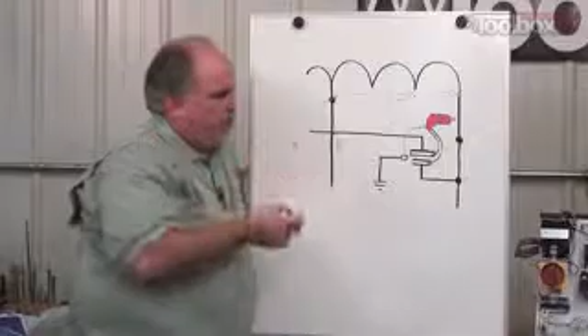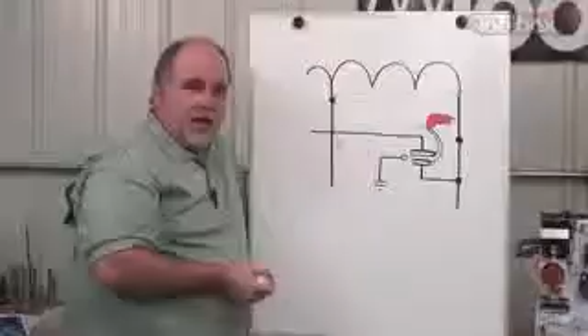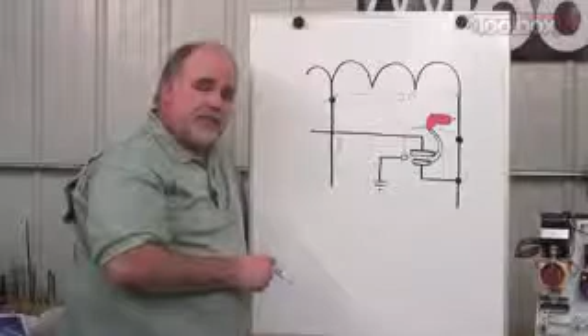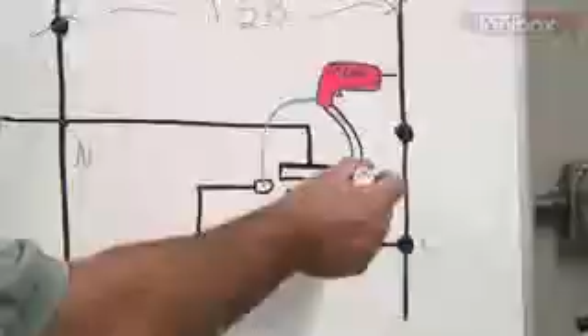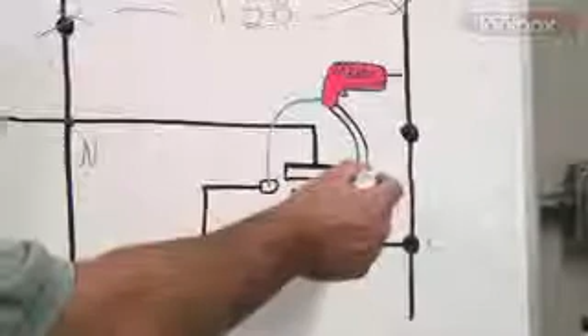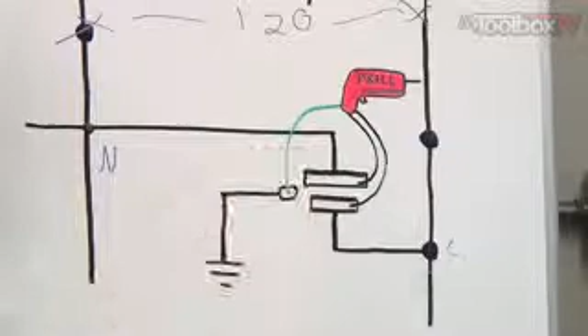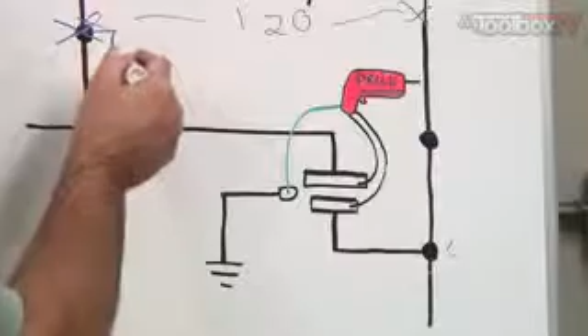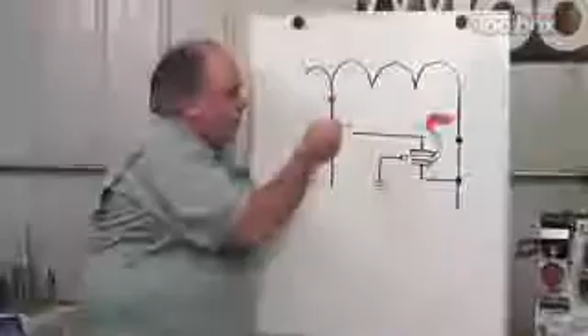Now let's say this happens, what then is going to be the case? Current can take a shortcut back to the receptacle because you've changed how the circuit is made. Current leaves the receptacle, grounds out to the case, and finds an easier path back to the receptacle through the ground wire, because the ground wire is also connected to this neutral point right here. The neutral point and the ground wire are connected together at the service equipment. That green wire gives you a safe path for fault current.